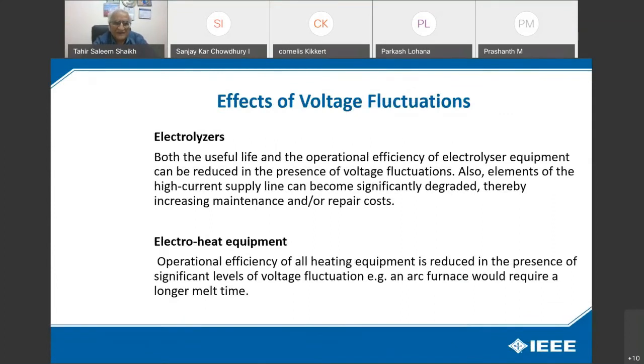Electrolyzer. Both the useful life and the operational efficiency of electrolyzer equipment can be reduced in the presence of voltage fluctuation. Also, elements of the high current supply line can become significantly degraded, thereby increasing maintenance or repair cost. Operational efficiency of all heating equipment is reduced in the presence of a significant level of voltage fluctuation. For example, an arc furnace would require a longer melt time.